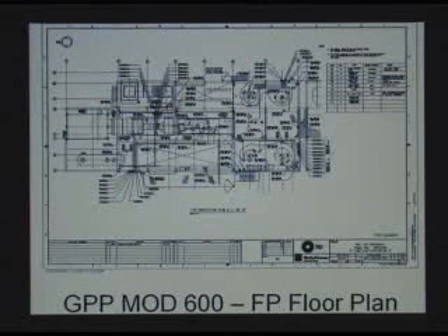And this is our fire detection, which is very hard to read. We're showing our flame detectors and gas detectors. We normally provide a lot of gas detectors near the bottom, where the equipment produces hydrocarbons. We deal with process people to find out where the high hydrocarbon-producing equipment is. So we provide gas detectors on the bottom, and also, because of maintenance and lighter-than-air gases, like I said, we put detectors all over the module.